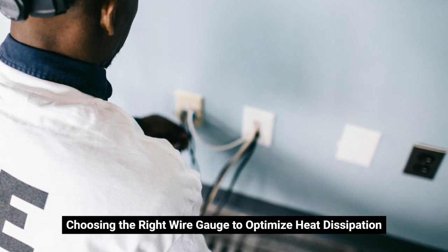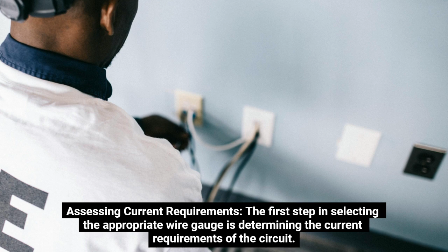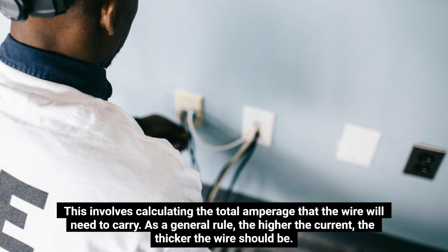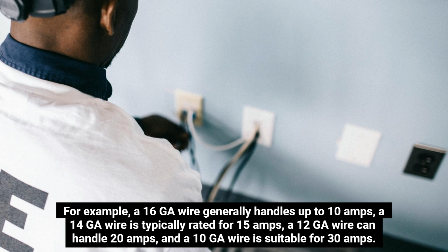Choosing the right wire gauge to optimize heat dissipation. Assessing current requirements. The first step in selecting the appropriate wire gauge is determining the current requirements of the circuit. This involves calculating the total amperage that the wire will need to carry. As a general rule, the higher the current, the thicker the wire should be. For example, a 16 GA wire generally handles up to 10 amps, a 14 GA wire is typically rated for 15 amps, a 12 GA wire can handle 20 amps, and a 10 GA wire is suitable for 30 amps.